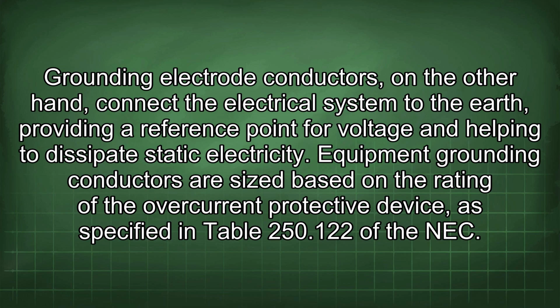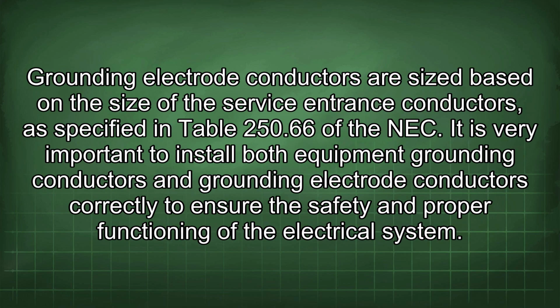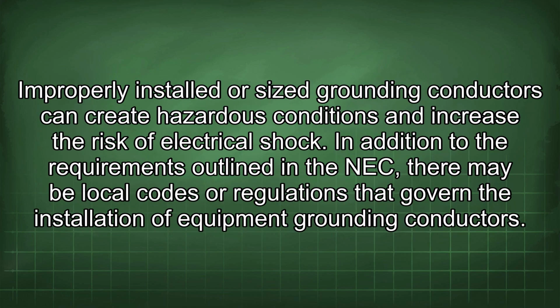Equipment grounding conductors are sized based on the rating of the overcurrent protective device, as specified in Table 250.122 of the NEC. Grounding electrode conductors are sized based on the size of the service entrance conductors, as specified in Table 250.66 of the NEC. It is very important to install both equipment grounding conductors and grounding electrode conductors correctly to ensure the safety and proper functioning of the electrical system. Improperly installed or sized grounding conductors can create hazardous conditions and increase the risk of electrical shock.